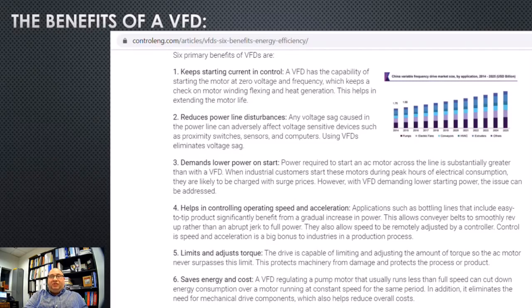There's 6 primary benefits of a VFD. This is something that I took from a generic blog on the internet. The reason being is that there's more benefits than disadvantages. So what we do is we keep the starting current in control, which is very important. There is something that is known as peak load demand, when we can limit the amount of inrush current that a building utilizes. All right, they keep their utility bills down for that month actually.